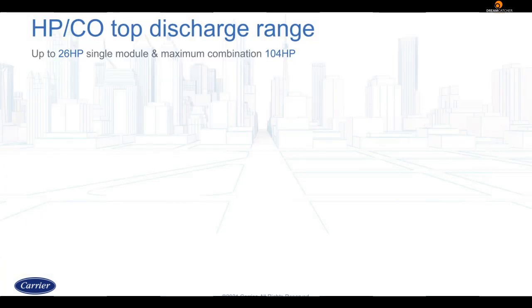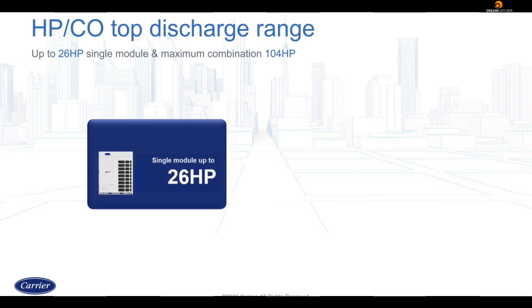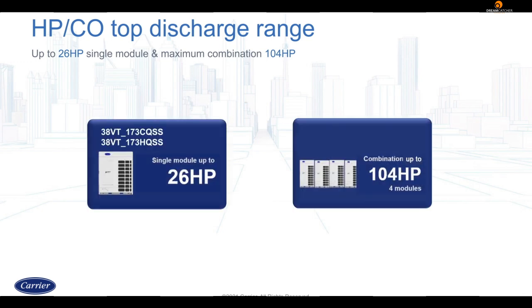The heat pump and cooling only top discharge models come in several variations. But let us first understand their nomenclature. 38V stands for VRF outdoor unit. T stands for top discharge. The next space is filled with the capacity of the unit. For example, if it's a 26 HP unit, 38VT will be followed by 026. The next letter represents whether it's a single module or a combination. 1 is used for single and S for combinations.